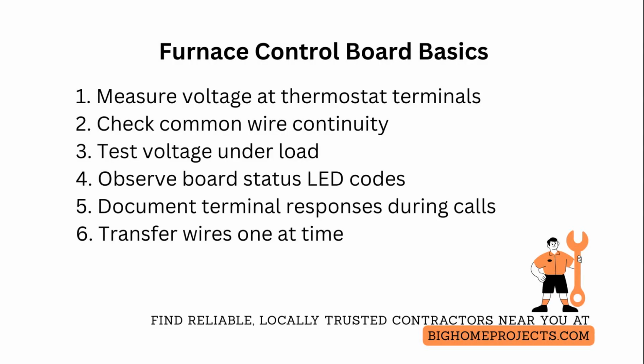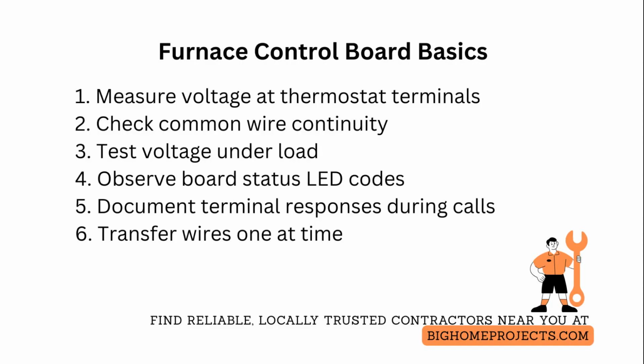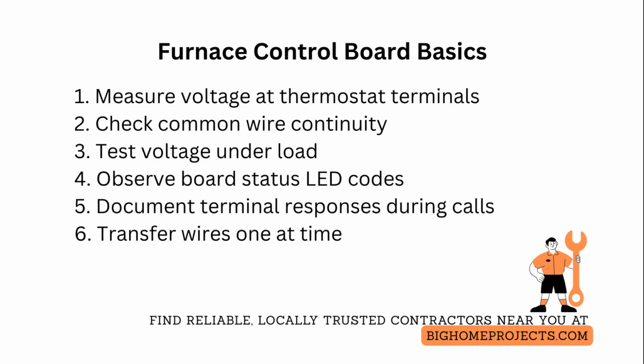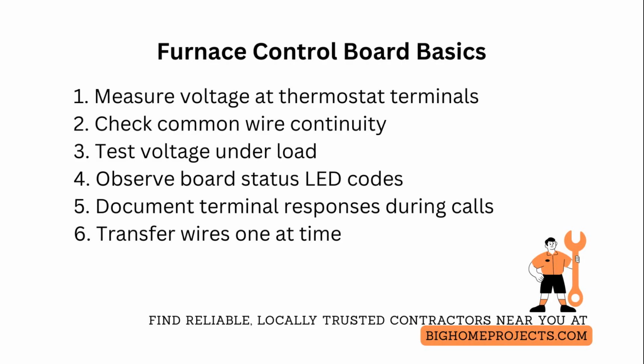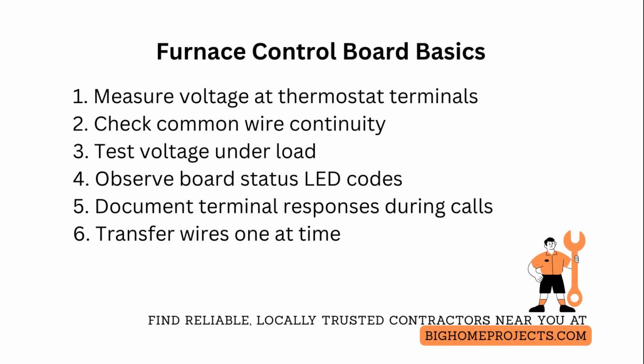Verify ignition sequencing by observing the board's status LED codes or by reading the service manual sequence table. A stalled inducer before ignition usually points to blocked venting, failing pressure switch, or a board that is not completing the safety loop. Use a multimeter set to low voltage DC where applicable and to AC for transformer outputs, and document terminal responses when you actuate thermostat calls. This creates a reliable reference if you must swap the board.